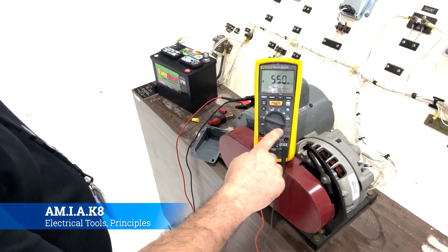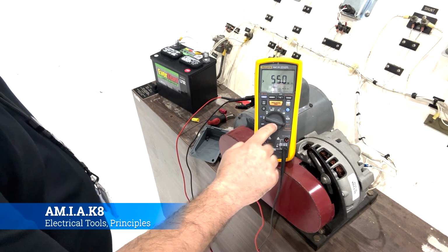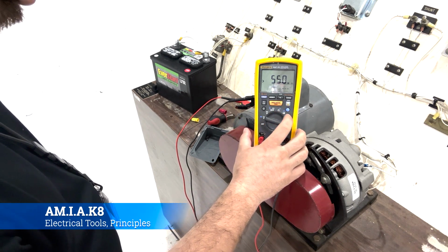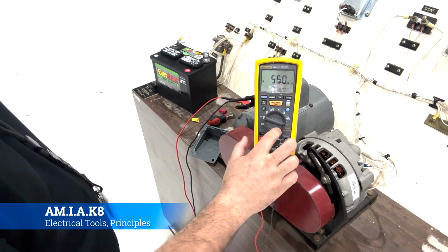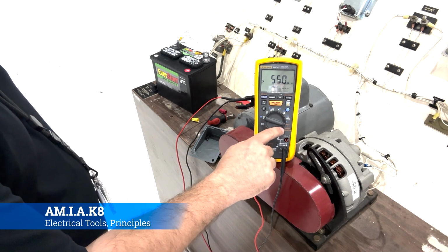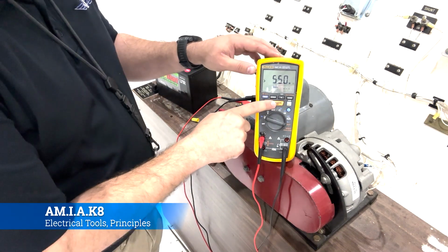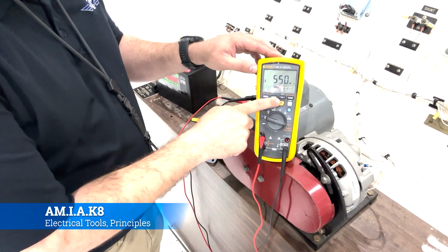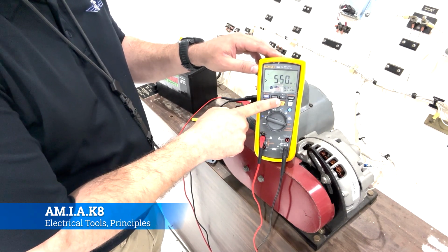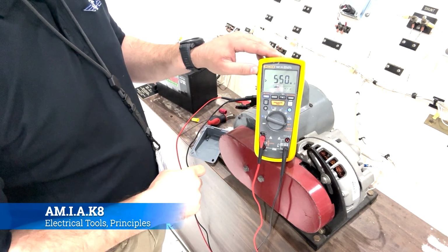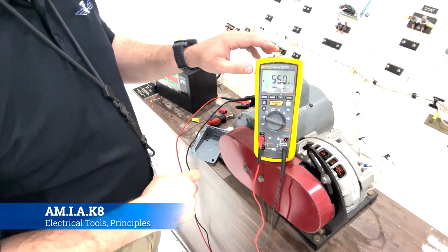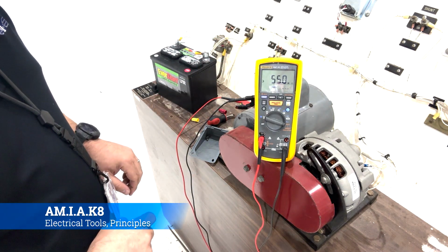Okay, so this is a megaohmmeter. Notice that it's set to insulation test. We're going to test the resistance on all three phases of our AC generator on our trainer. It's an AC motor that turns our alternator for the trainer. So it's hooked up to the first phase. We're going to press insulation test and hold it until we get a reading. Notice that it's greater than 550 mega ohms.